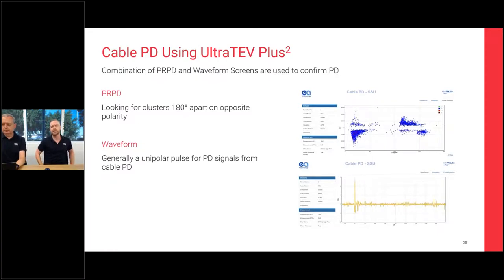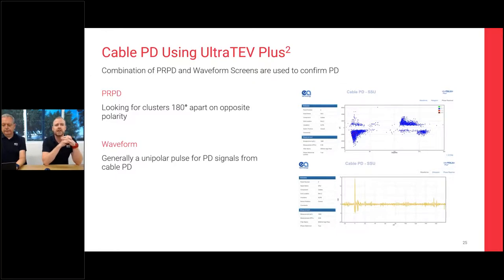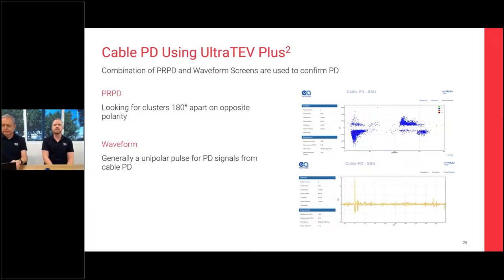The UltraTEV Plus 2 — the handheld piece of kit as opposed to the cable data collector — can also take snapshots with an RFCT. You hook it onto the earth screens of cables and it captures PD signals bouncing up and down the cables. You can see a phase-resolved partial discharge pattern, looking for clusters 180 degrees apart along the sine wave. You'll also capture those waveforms and fast high-frequency pulses. You can also apply the filters into the UltraTEV Plus 2 and the readings come out basically the same as on the cable data collector.